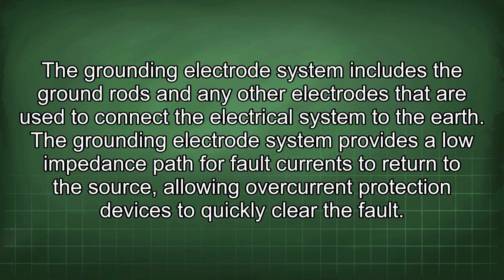The grounding electrode system includes the ground rods and any other electrodes that are used to connect the electrical system to the earth. The grounding electrode system provides a low impedance path for fault currents to return to the source, allowing overcurrent protection devices to quickly clear the fault.